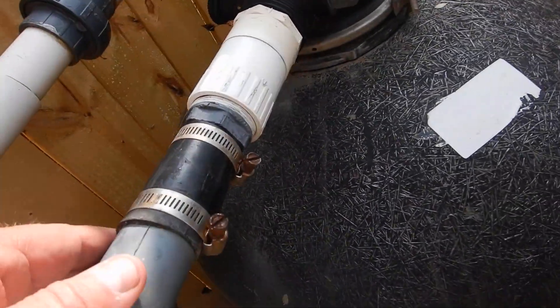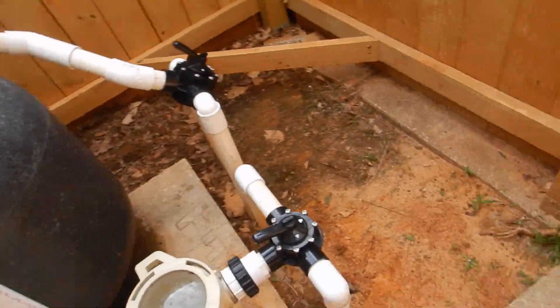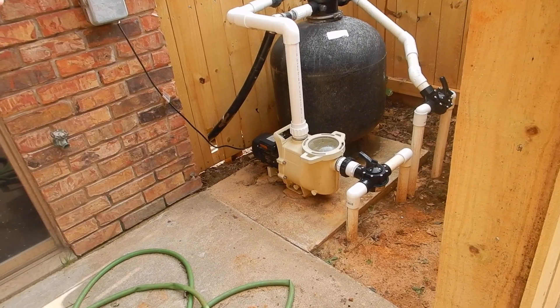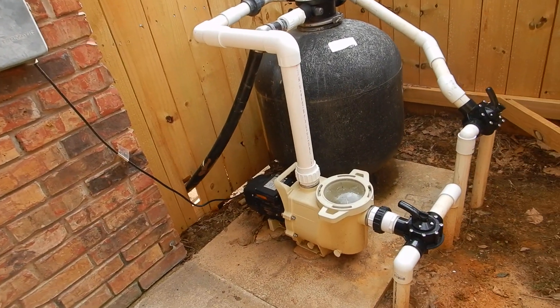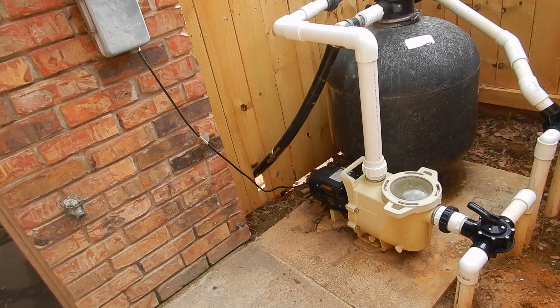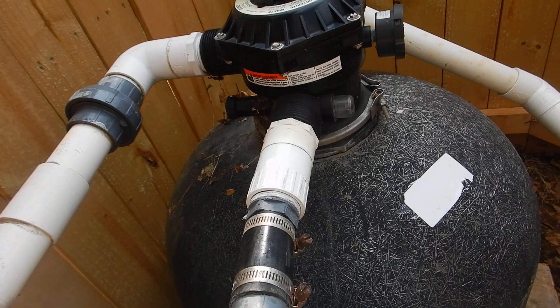This is the straw I was telling you about. This is your backflow. I guess you've got a vacuum breaker for the drain because it just goes out to the air. Check with your municipality. This arrangement isn't that unusual — it doesn't make it right. It's a common workaround.